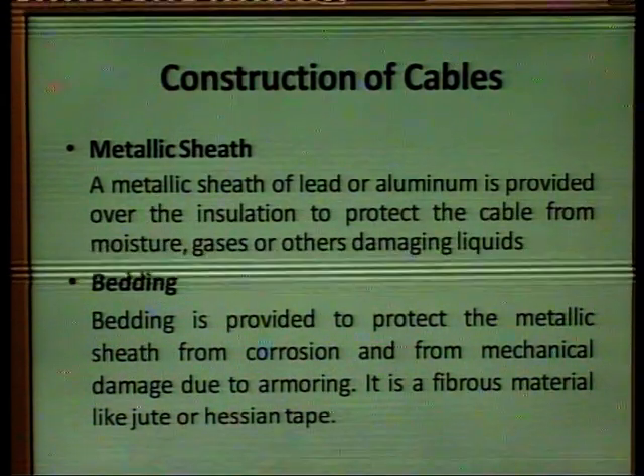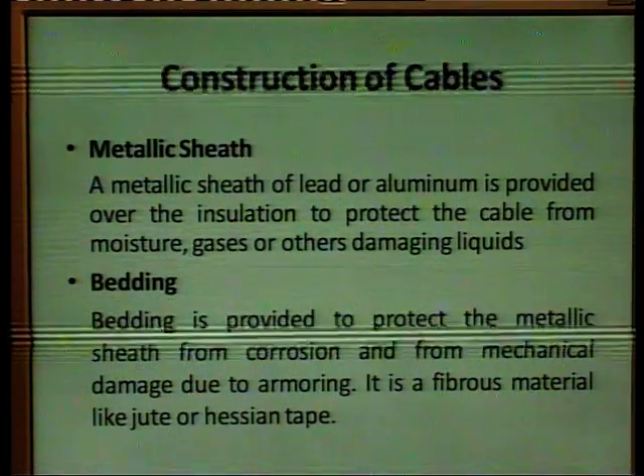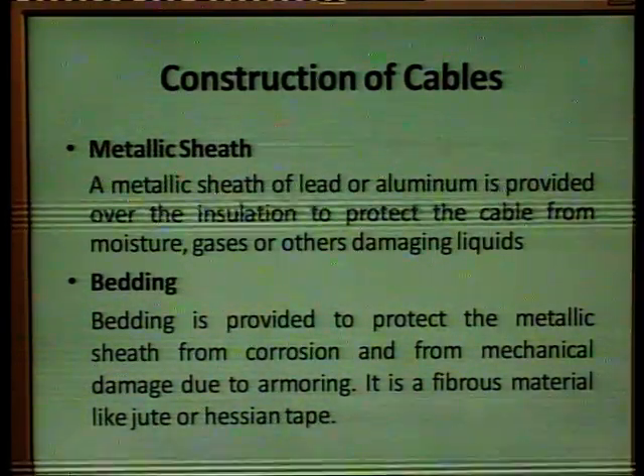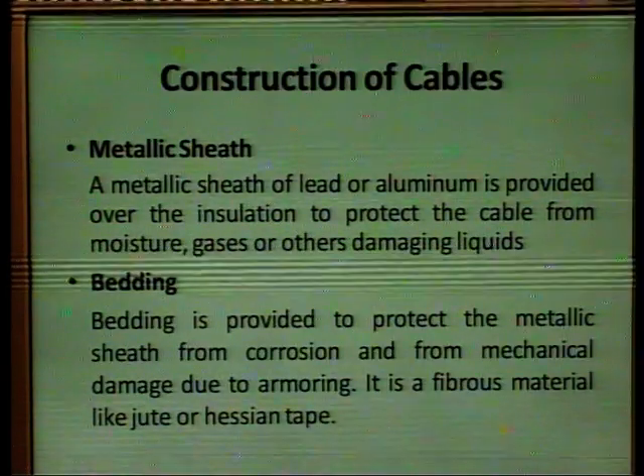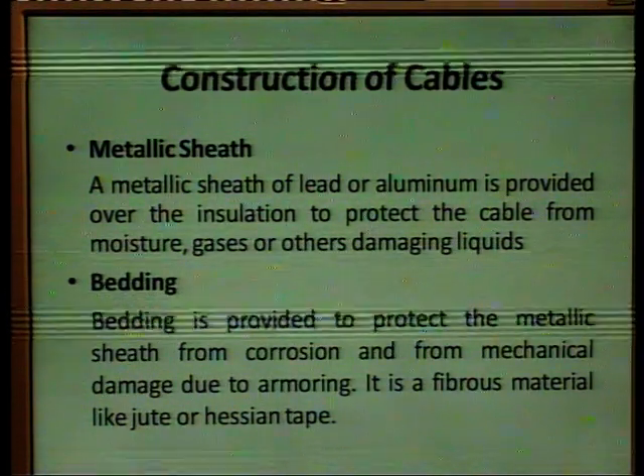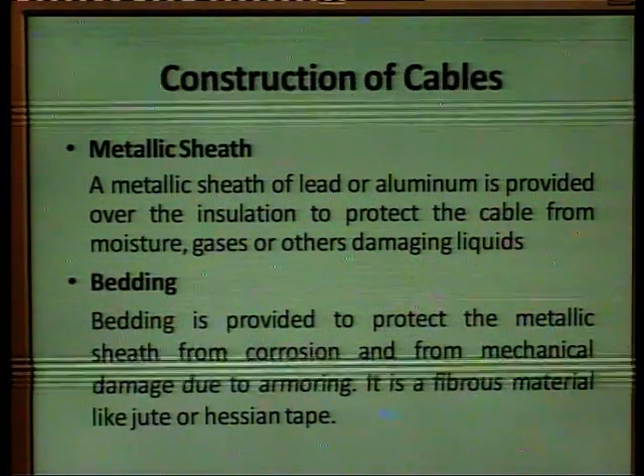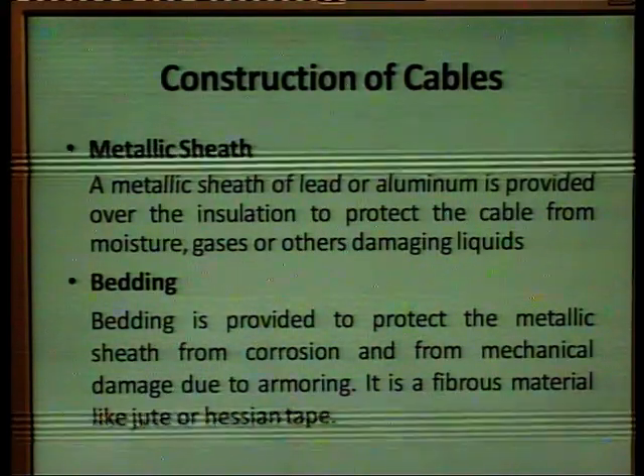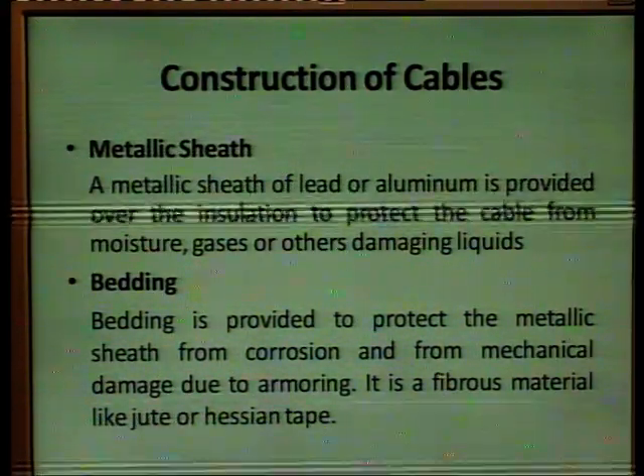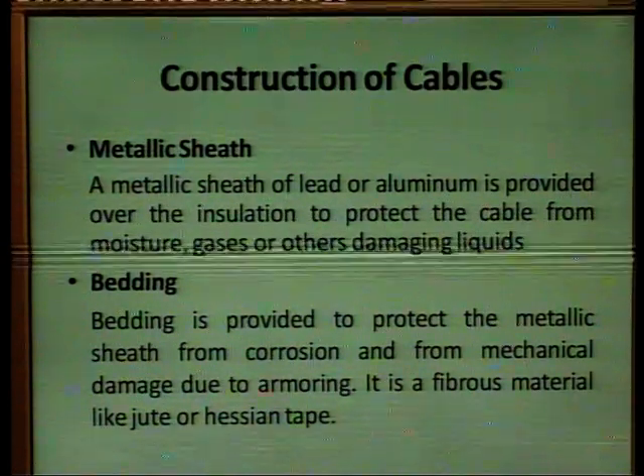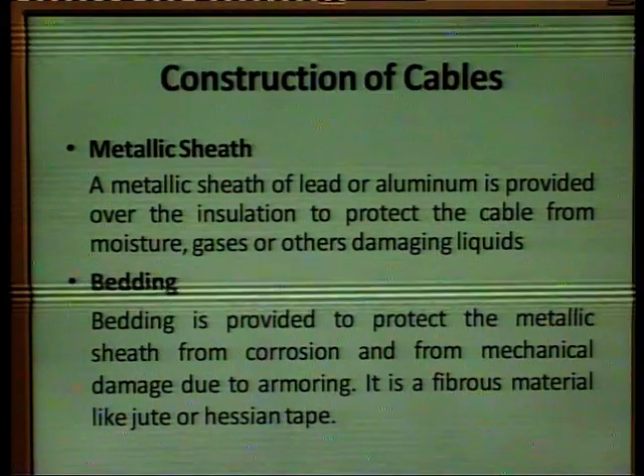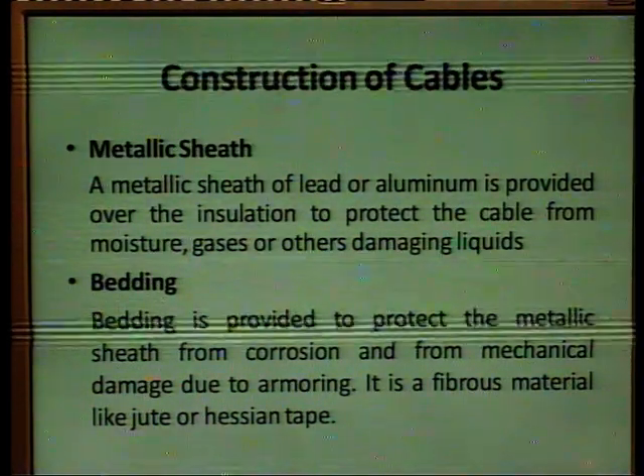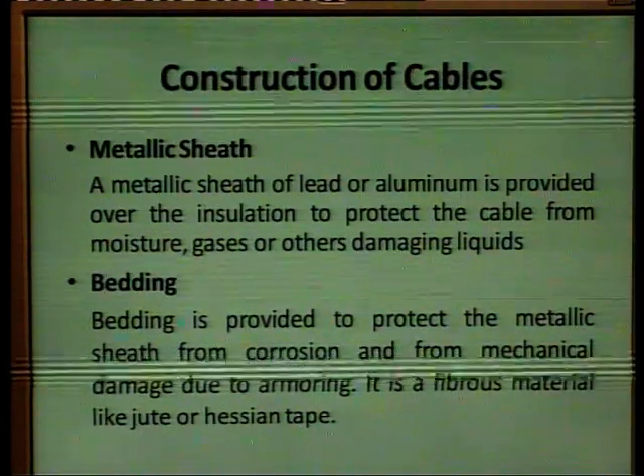Then we have the metallic sheath. The metallic sheath of lead or aluminium is provided over the insulation to protect the cable from moisture, gases, or other damaging liquids. Then the bedding. The bedding is provided to protect the metallic sheath from corrosion and from mechanical damage due to the armoring. It is a fibrous material like jute or Hessian tape.